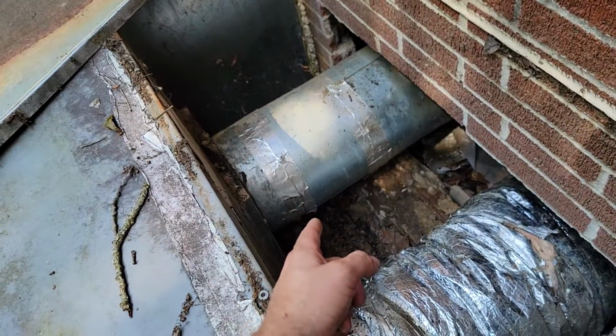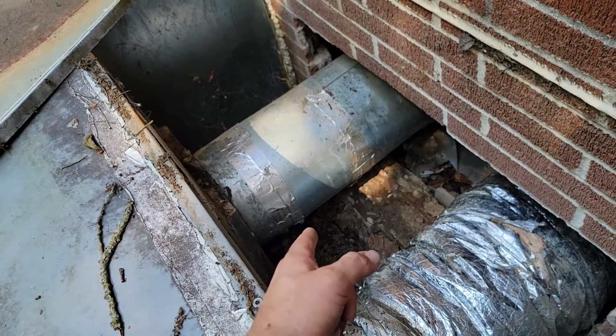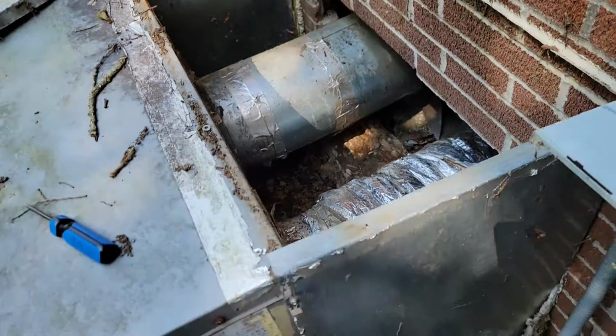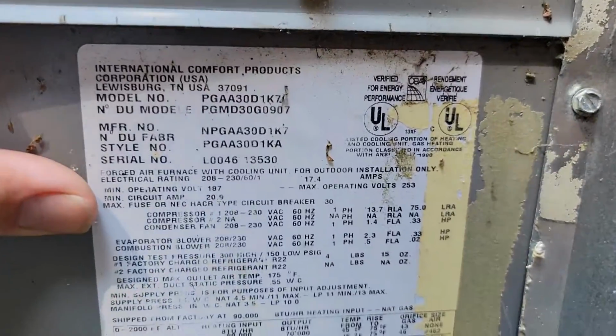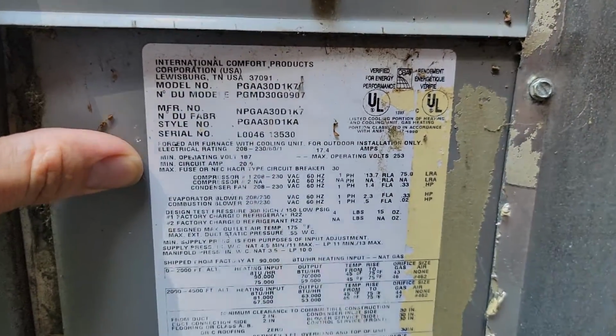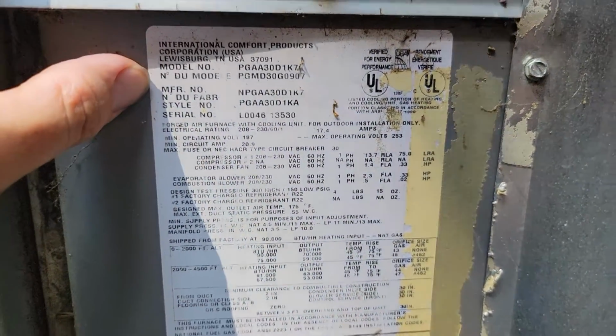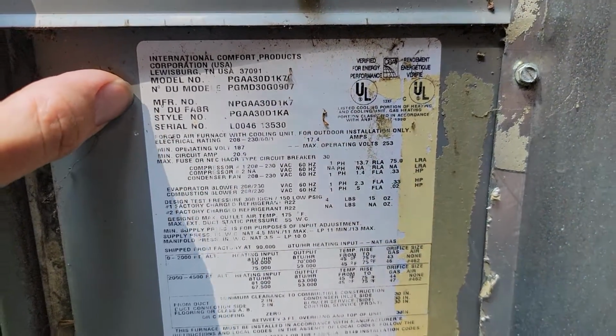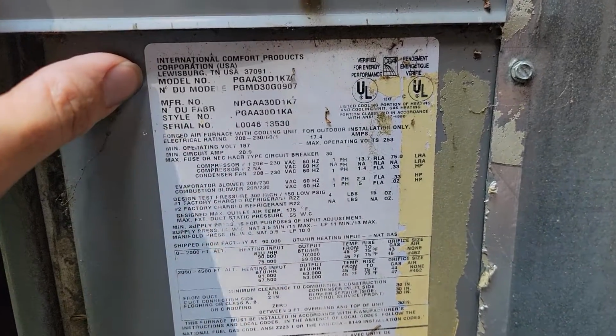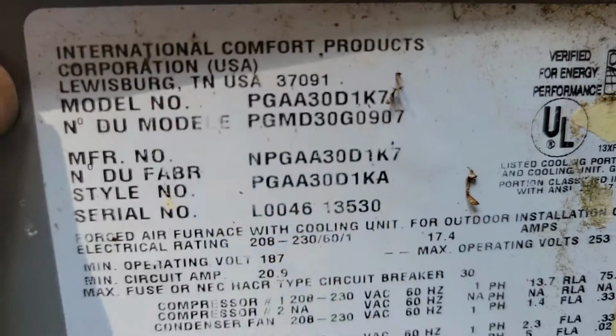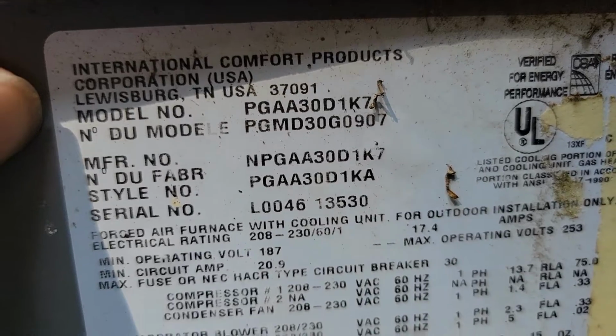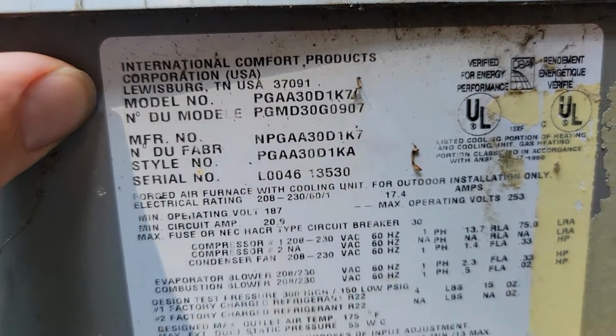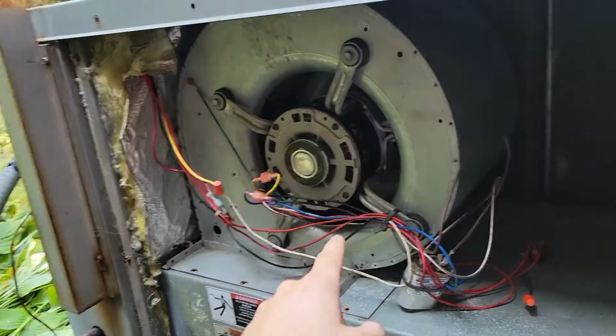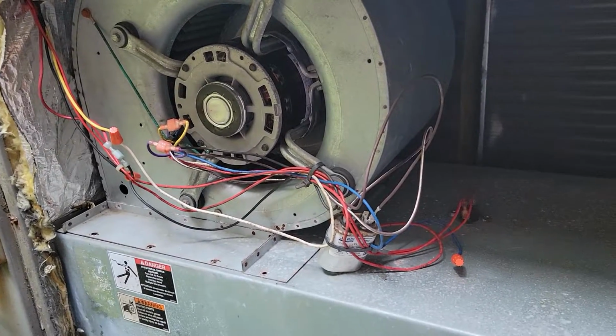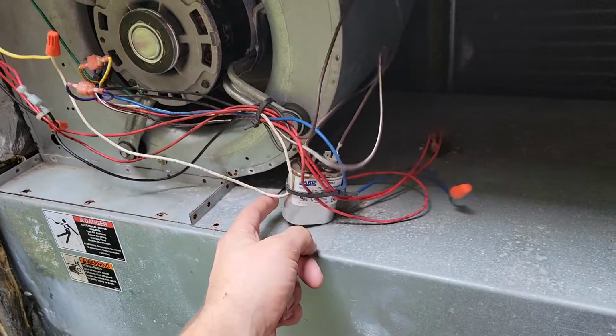Let's take a look at this ductwork real quick. So that right there looks like probably 10, 12 inch. Let's look at the model and serial number. 2.5 ton. Now I know right off the bat, I'm pretty sure 2.5 ton needs at least 14, 15 inches. So this duct is undersized. And I know it's a 2.5 ton because it says 30,000 BTUs right there. PGAA 30. So 2.5 ton. Looks like somebody's put a universal motor on here. That's nice. Look at that.